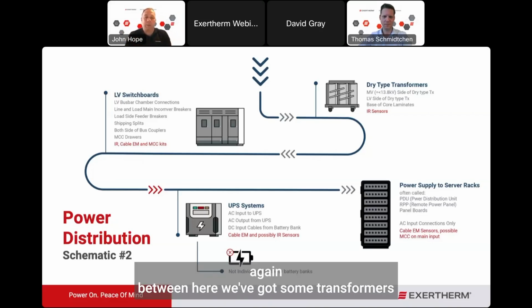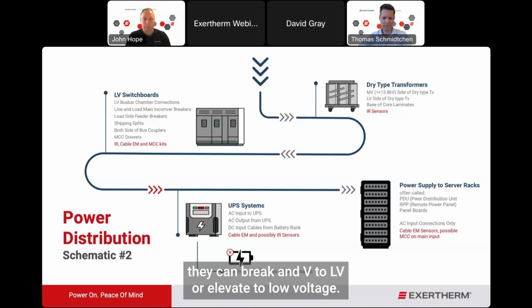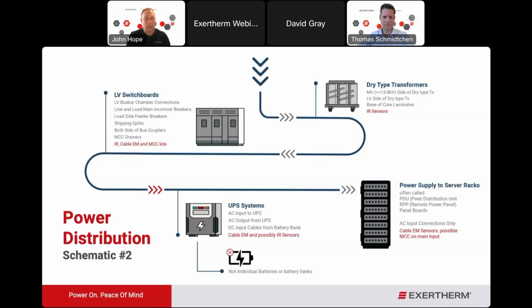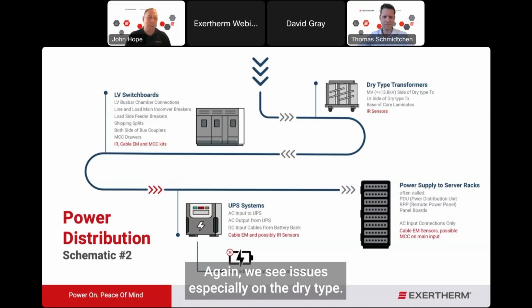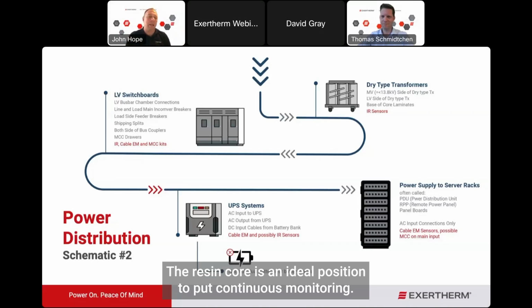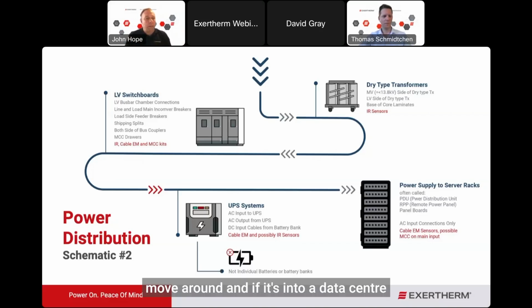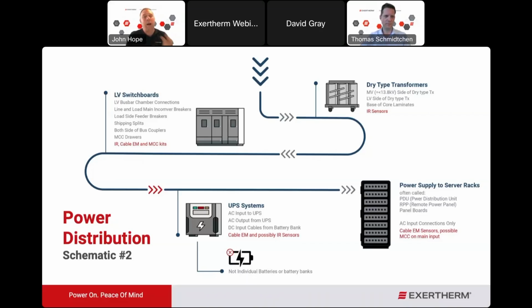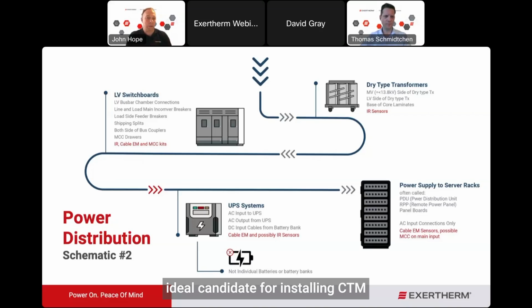Again, between here, we've got some transformers. They can be MV to LV or LV to low voltage. Again, we see issues, especially on the dry type, the resin core. It's an ideal position to put continuous monitoring. We then move round, and if it's into a data center market, we'll see UPS systems, so that uninterruptible power supply. And again, an ideal candidate for installing CTM.